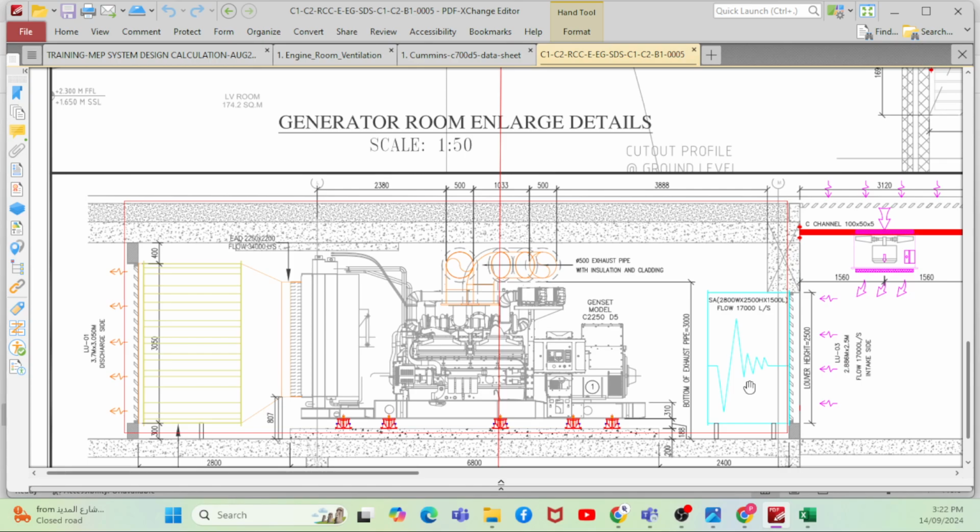But then generally these generator rooms are something that we always say are naturally ventilated, right? There will be a scenario where you would have open doors, or doors with a different mesh. That I will explain in the next, different concept. This is the situation if you have a closed room. What we calculated is based on the ventilation airflow required.